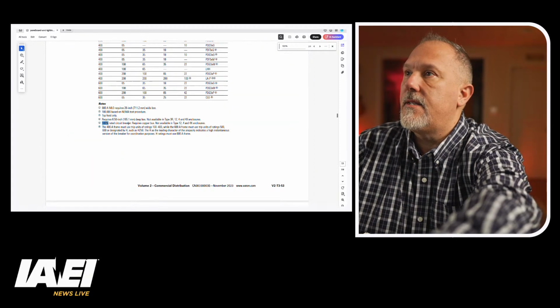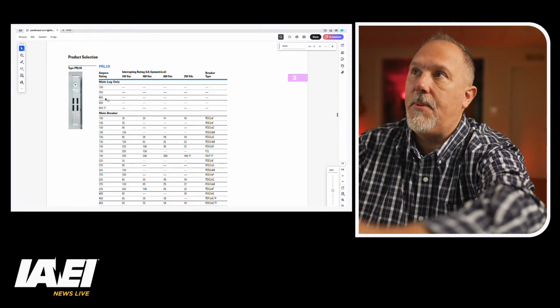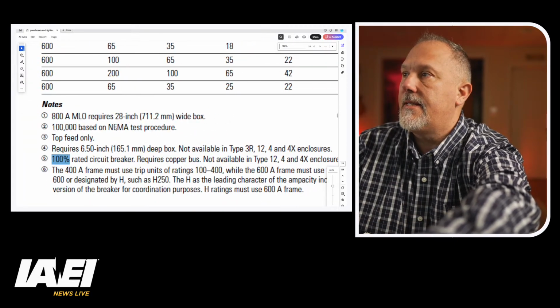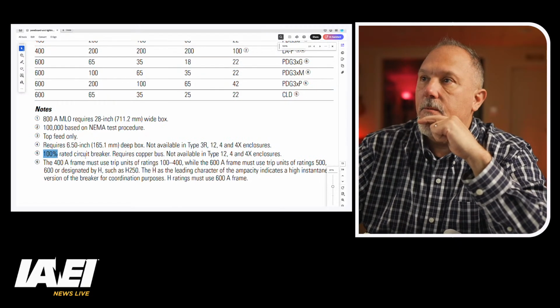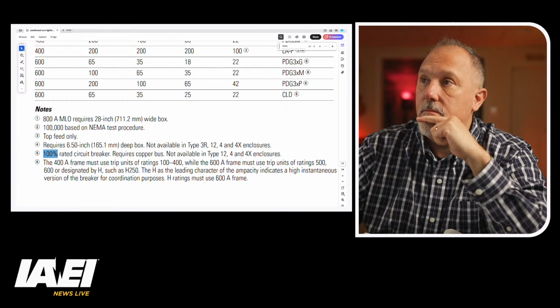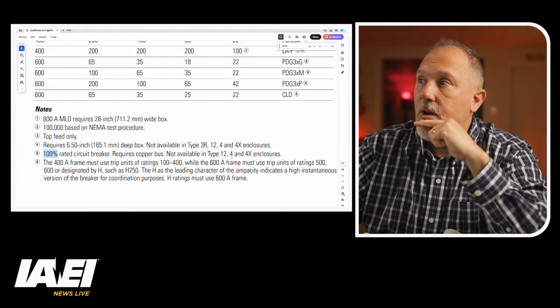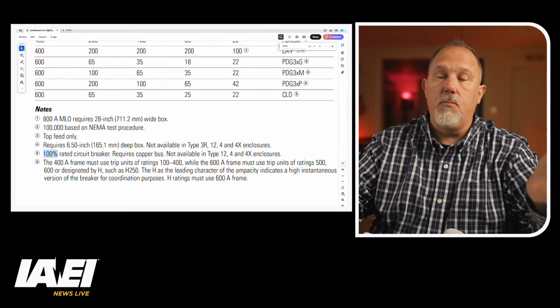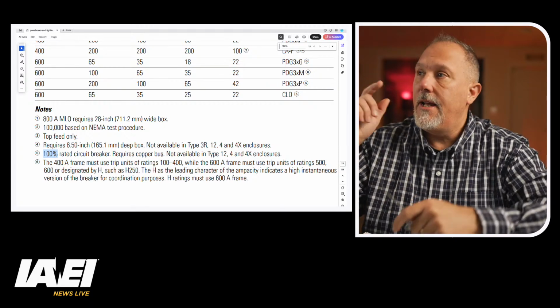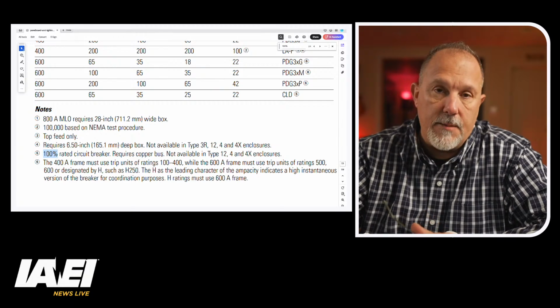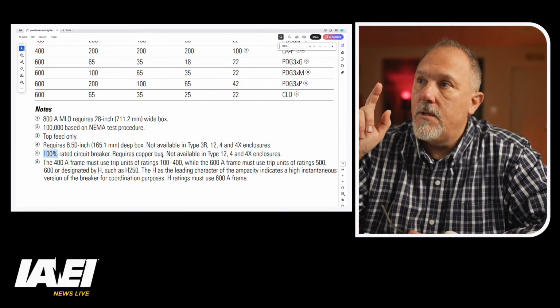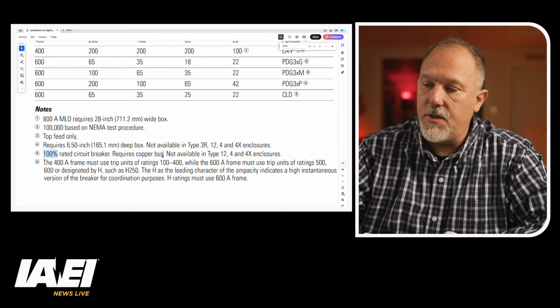And then look at this. Now this is the panel board. So this is just a panel board from a manufacturer. And it says right here, 100% rated circuit breaker requires copper bus, not available in type 12, 4, and 4X enclosures. So this manufacturer for this specific model of a panel board tells you it has to have a copper bus and that it's not available in certain types of enclosures. So you have to consider the enclosure along with the overcurrent device. You just don't buy a circuit breaker, stick it in a panel board, and say, okay, now I'm 100% rated.